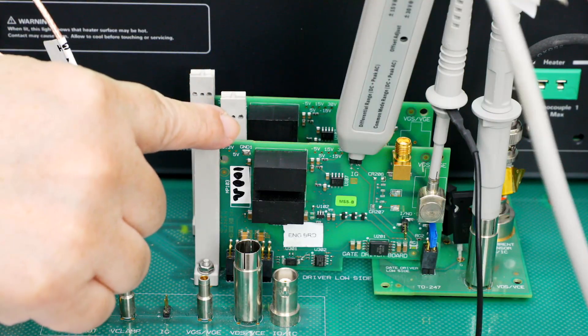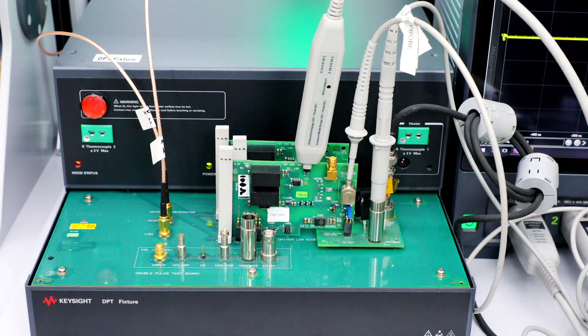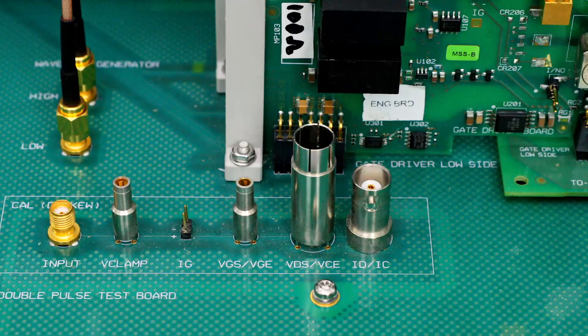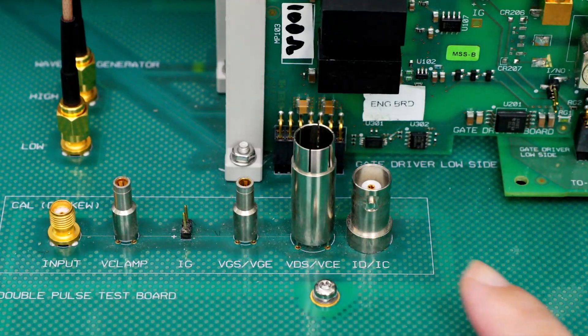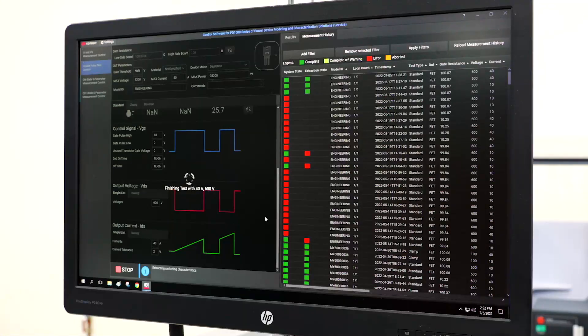The high side and low side gate drivers are over here, and you simply connect the current and voltage probes here to probe the device's switching characteristics. Over here are the oscilloscope probe connectors for the deskew calibration when necessary.